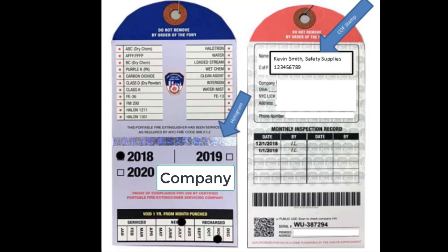Fire extinguisher locations will be outlined in the site-specific safety plan. All fire extinguishers on the project site must be visually checked on a monthly basis. Records must be kept and available for review.